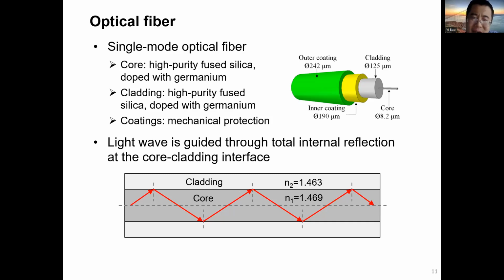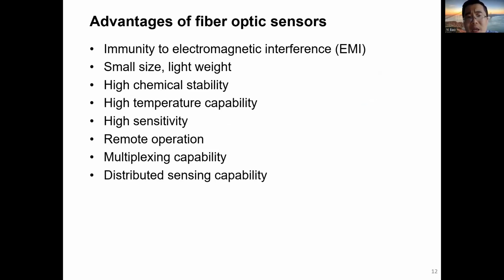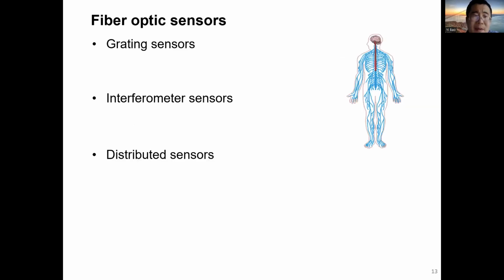Therefore, we can use fiber optic sensors as both distributed sensors and transmission lines with the same cable. There are some important advantages of fiber optic sensors, such as immunity to EMI effect, small size, lightweight, high chemical stability, temperature capability, and sensitivity. Also, fiber optic sensors can be operated remotely, and we can multiplex different sensors for distributed or quasi-distributed sensing. This talk will mainly focus on the fully distributed sensing capability.